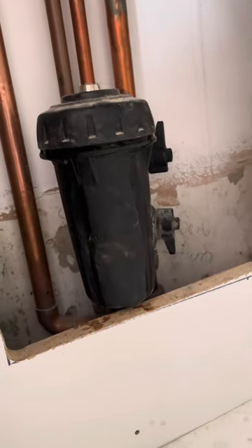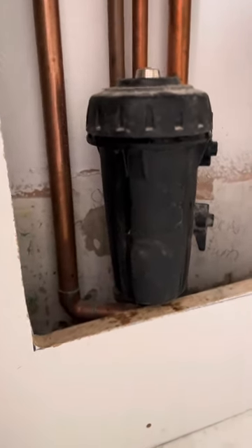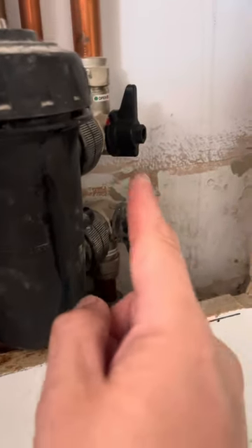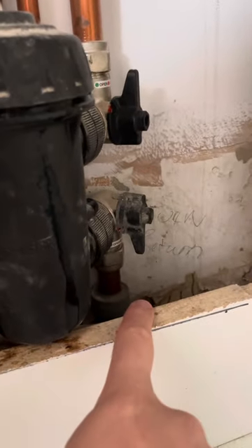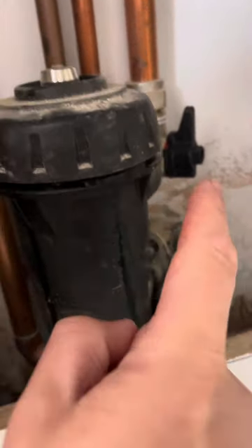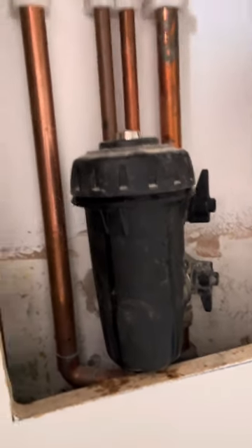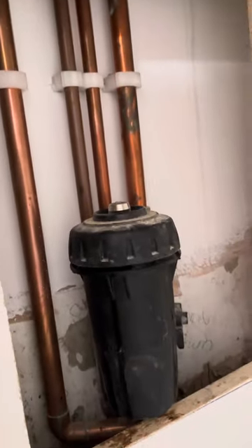Today we're changing the MagnaClean filter because it hasn't been changed for a while. I'm isolating the return — that's the flow back from the radiators into the MagnaClean filter, and then back up to the boiler. So I've isolated it and I've got my trusty tool which comes with the filter.